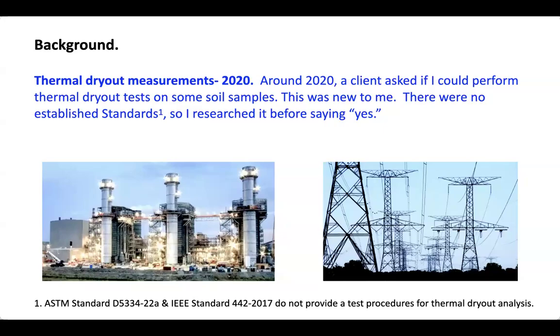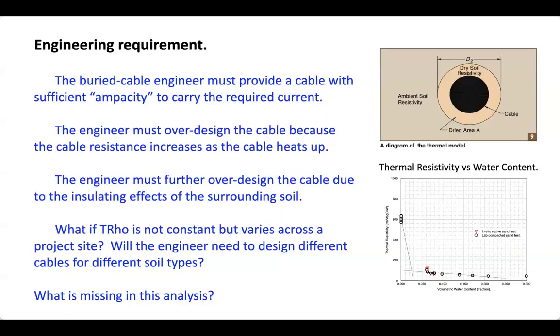Okay, so around 2020, a client asked if I could perform thermal dryout tests on some samples, and this was new to me. There were no established standards. I looked, and so I researched it before saying yes. And here's what's going on. Here's a little schematic. We're looking at a cross-section of the cable, which is the black dot, and then there's an area surrounding the cable where the heat is being dissipated into the soil.